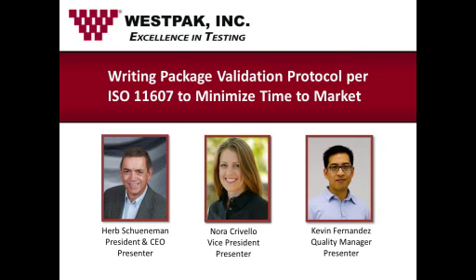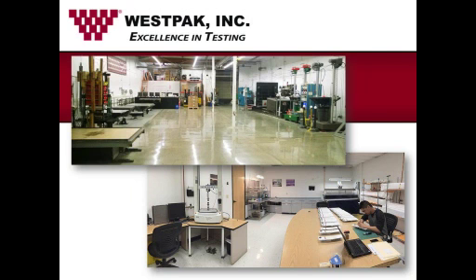As a test lab, we do a lot of package validation testing. We see and execute a lot of these package validation protocols for our clients. So that means that we do the climatic conditioning, we do the package performance testing, the accelerated aging, the bubble, the peel testing, the burst testing, pretty much all testing that you need to do in order to properly validate your medical device package system.